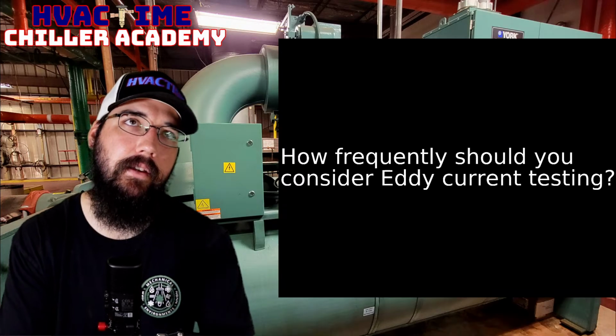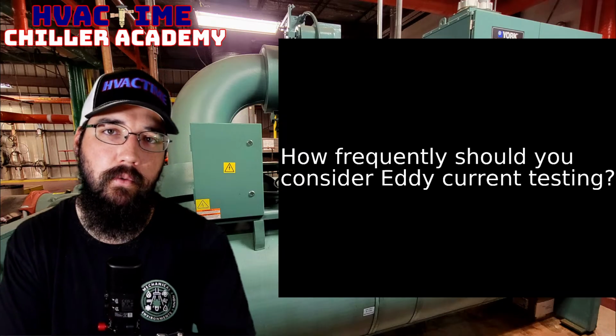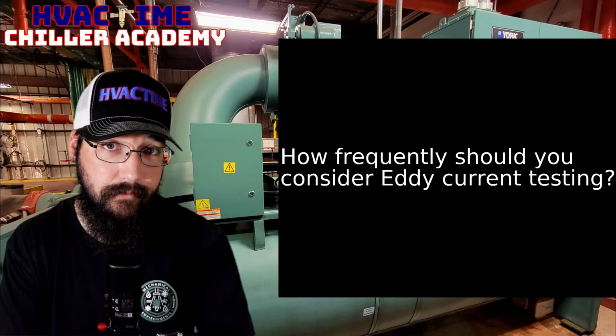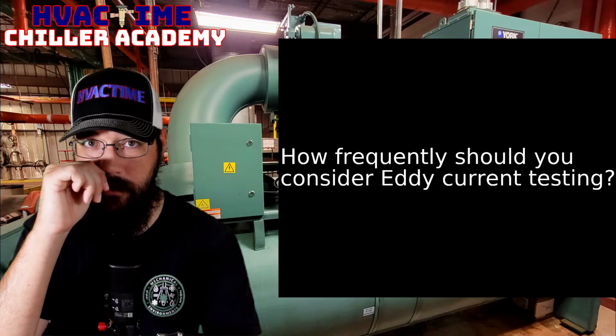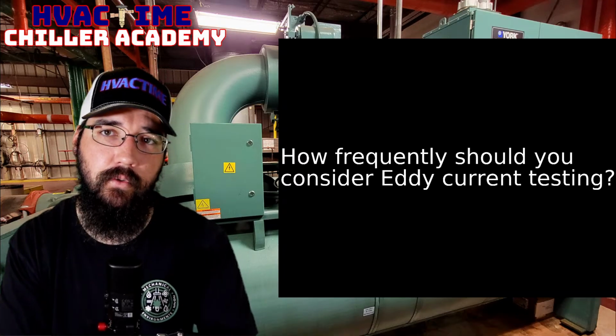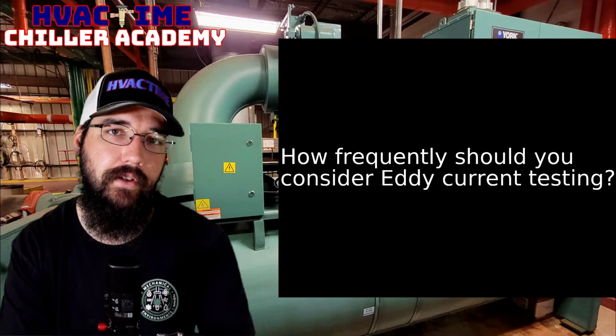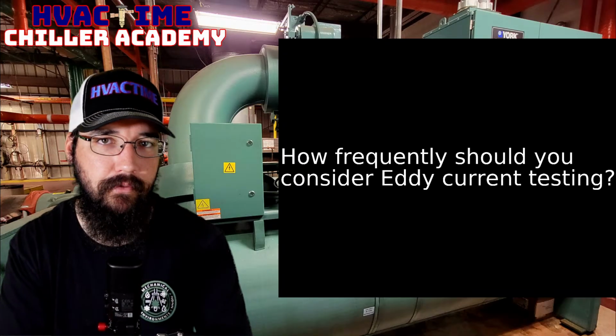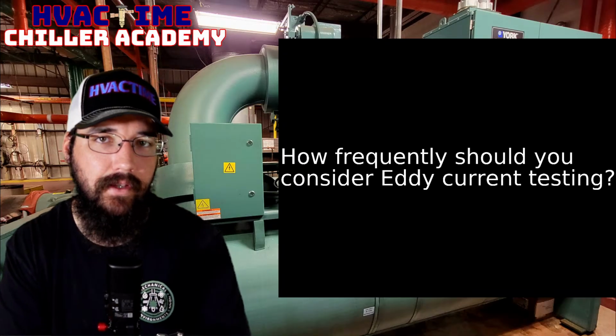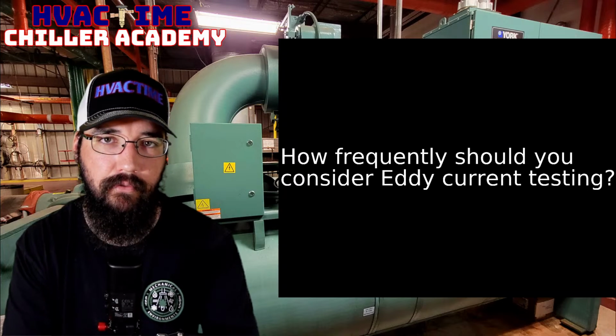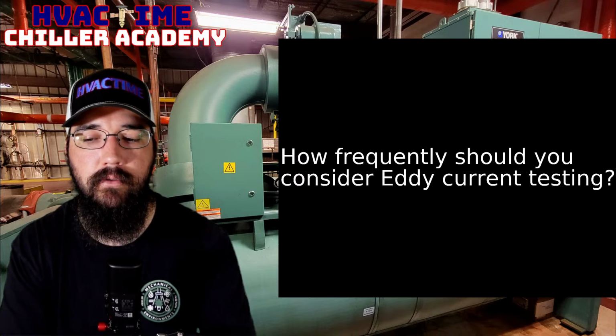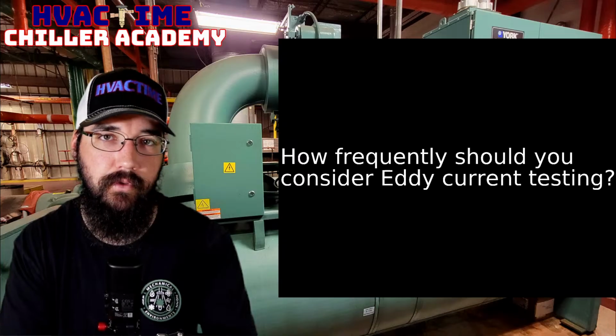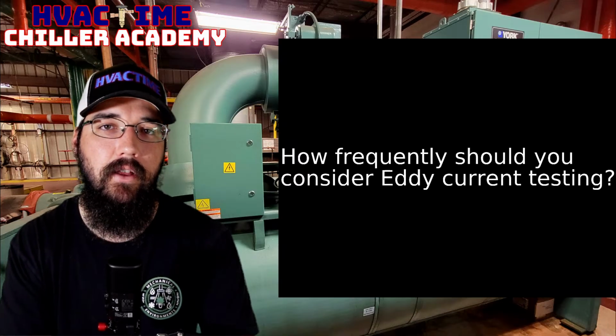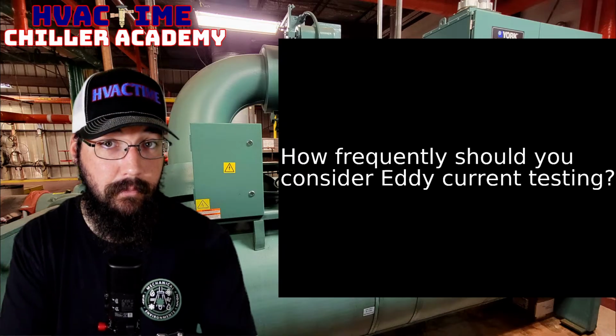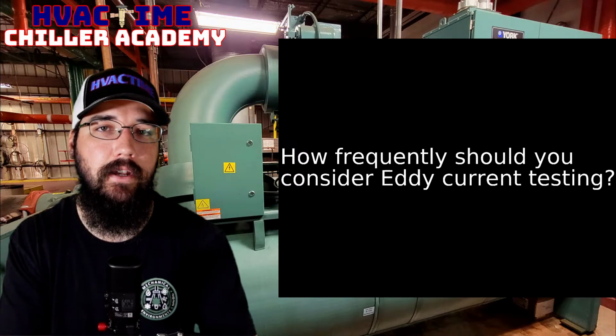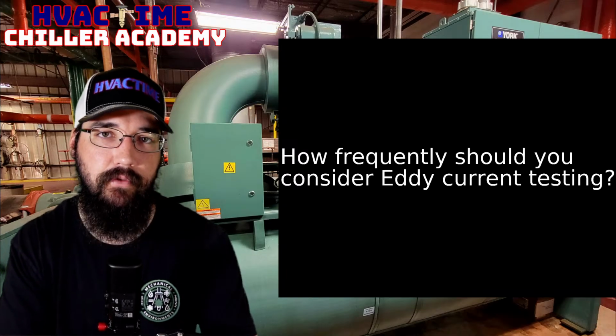If you're worried something didn't go right with a recovery or charging procedure, or if you're worried there could have been a freezing condition that formed, where water in those tubes could expand and cause damage, those are all good reasons in my opinion to do an eddy current prematurely before the 5-year mark.